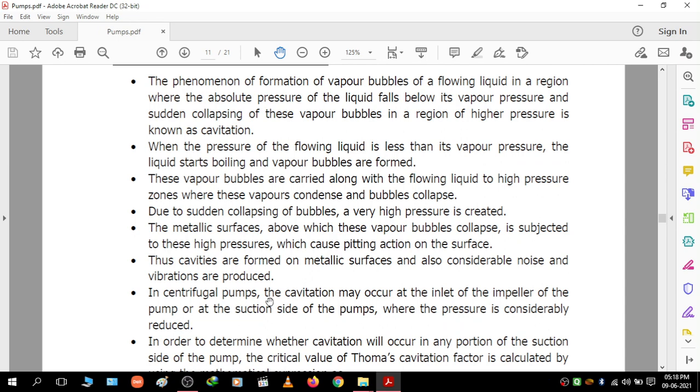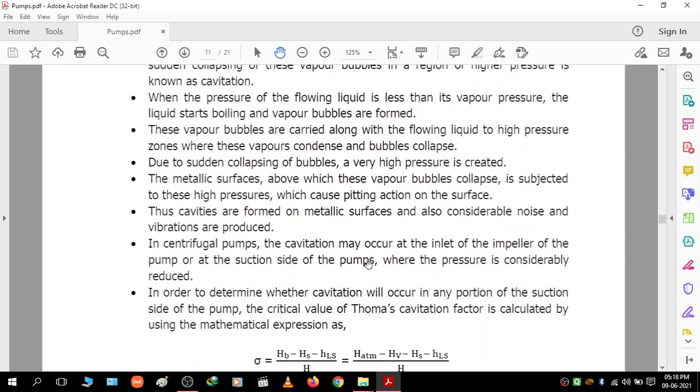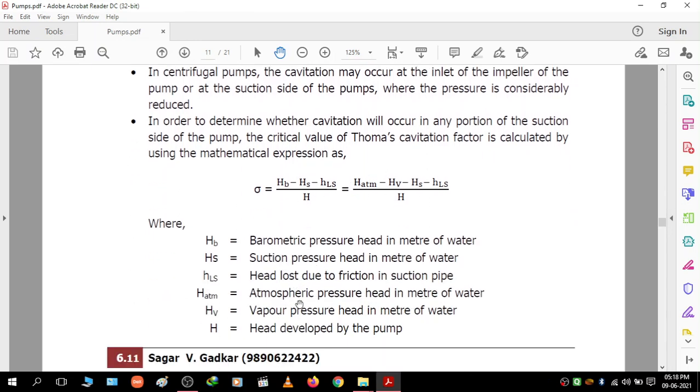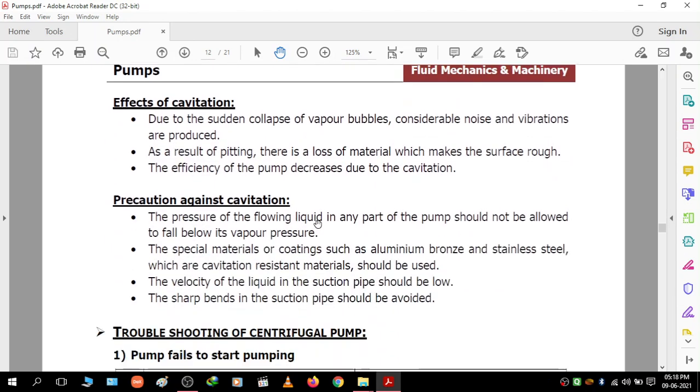In centrifugal pumps, the cavitation may occur at the inlet of the impeller or at the suction side of the pumps where the pressure is considerably reduced. The cavitation factor is calculated using specific equations. Due to the sudden collapse of vapor bubbles, considerable noise and vibrations are produced. As a result of pitting, there is loss of material which makes the surface rough. The efficiency of the pump decreases due to cavitation.